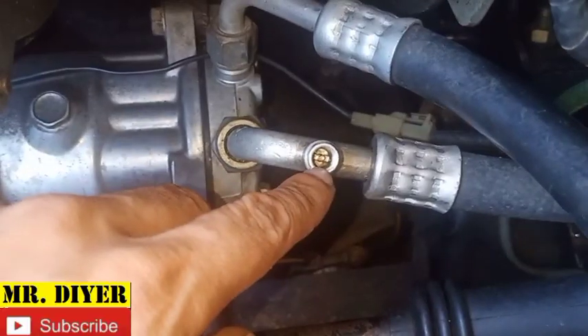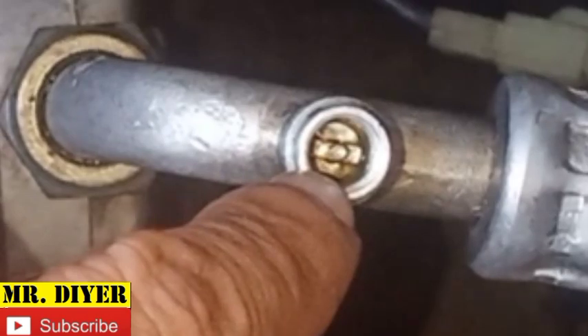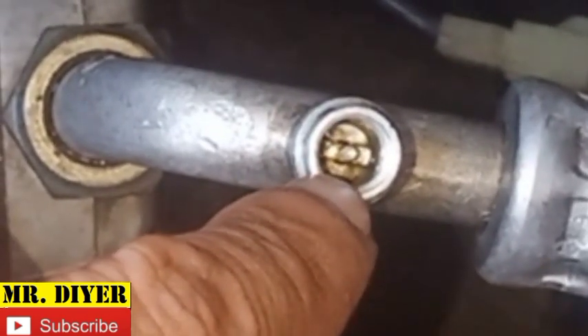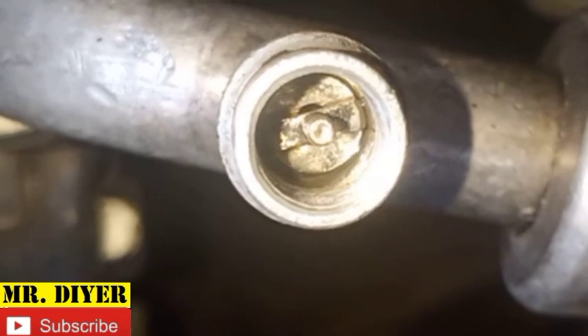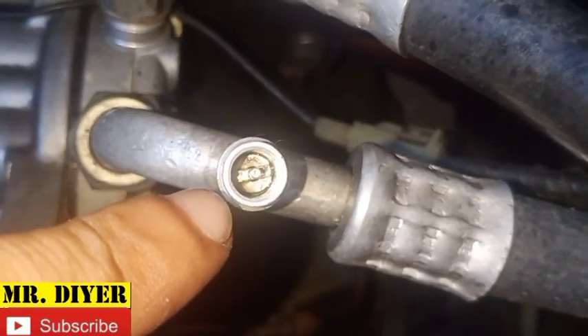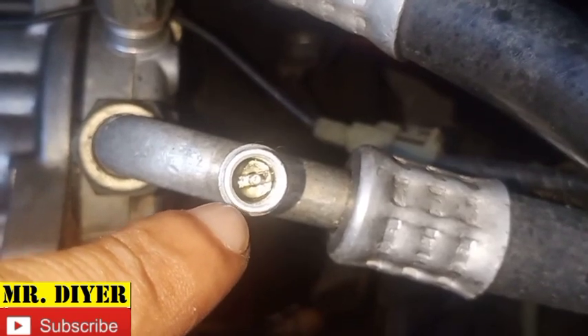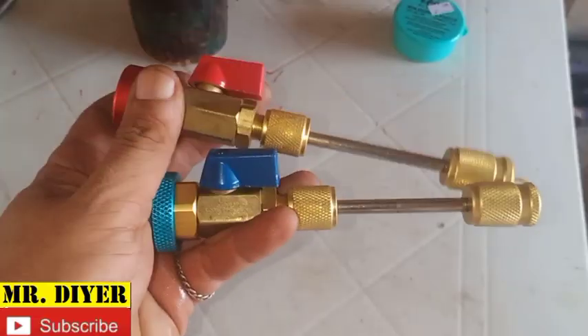Hello everyone, welcome back. In this video we'll show you how you can replace the valve or Schrader valve on your AC system without losing refrigerant. Say for example your valve is leaking — as you can see there are bubbles coming out, so that means there's a leak. We cannot just remove the valve and replace it with a new one because we will lose all our refrigerant, and we do not want that.